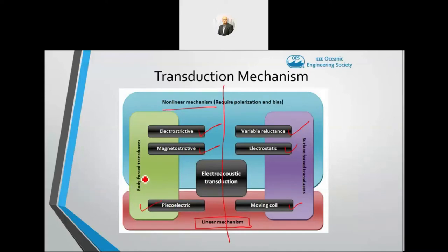Body force transducers, the simplest way to define them, is that the whole body of the transducer is utilized to convert the energy, compared to surface force transducers, where only a partial area, maybe the top or bottom part of the transducer, is used to transfer the energy. Today we'll be talking about piezoelectrics more than other transduction mechanisms, because it is simply the best and the most efficient way to convert electrical energy to acoustic energy, as well as to convert acoustic energy to electrical energy.